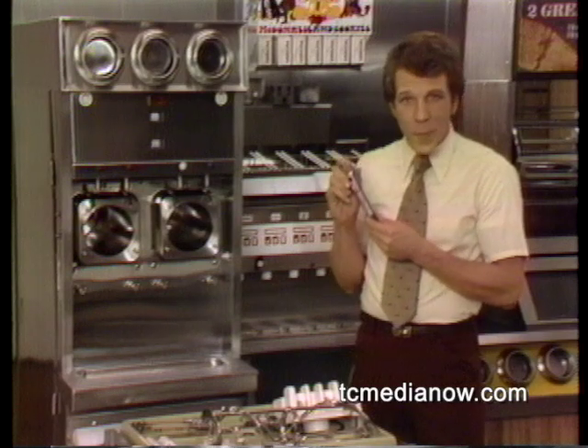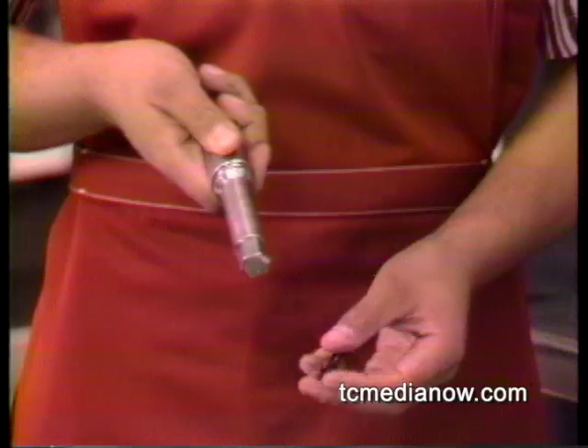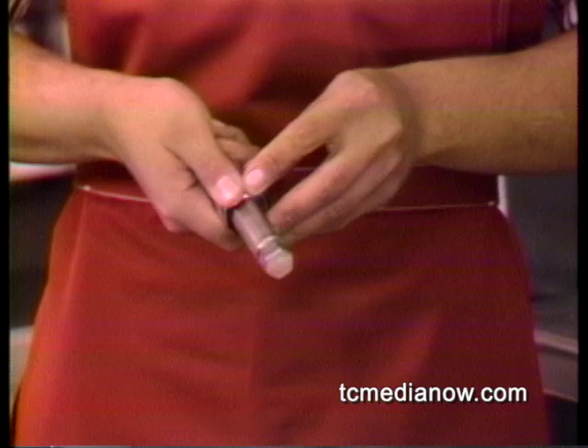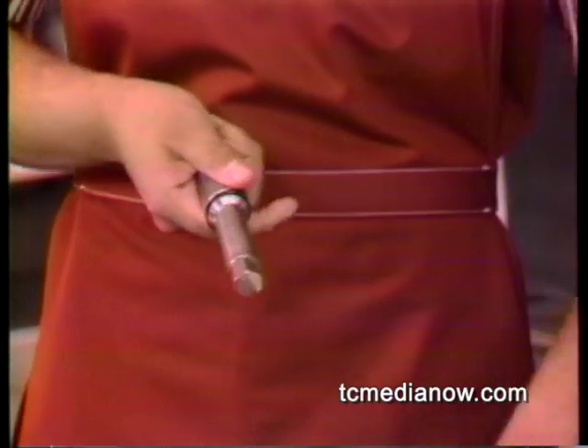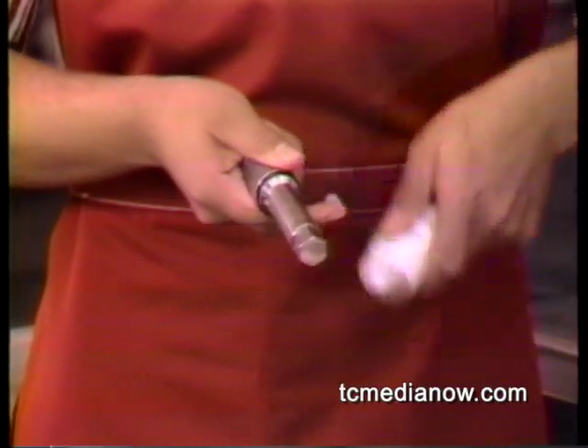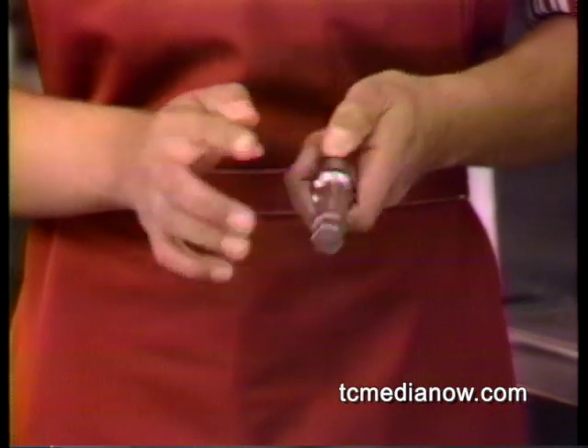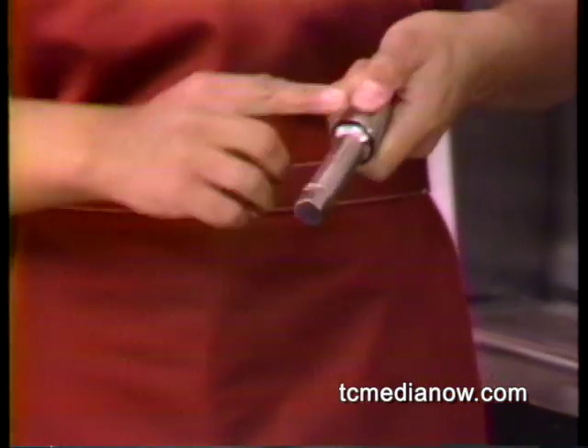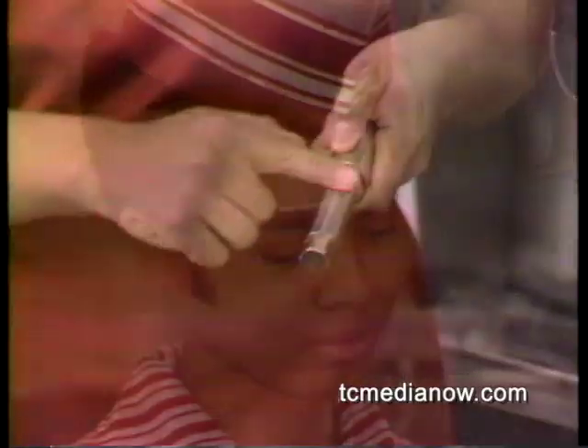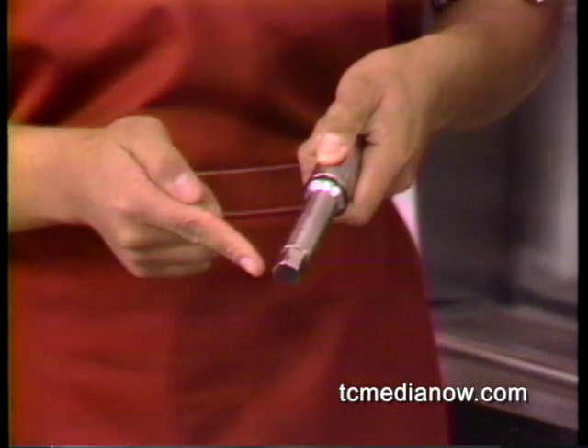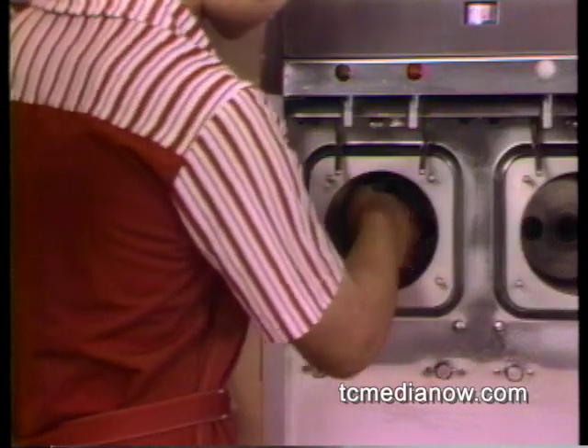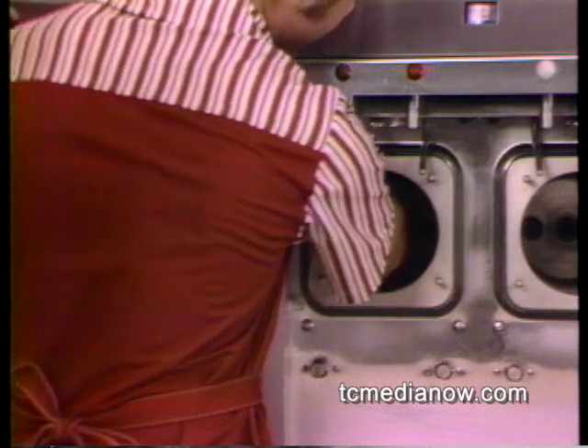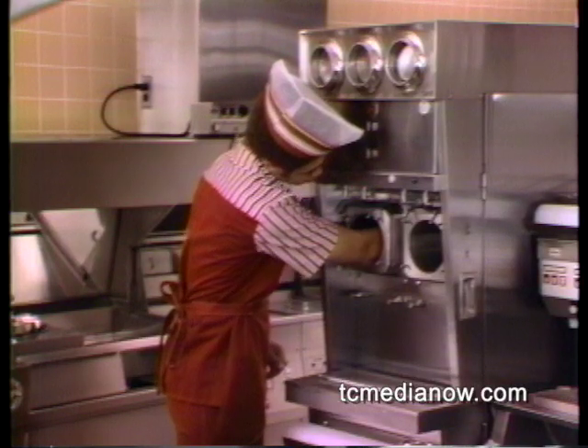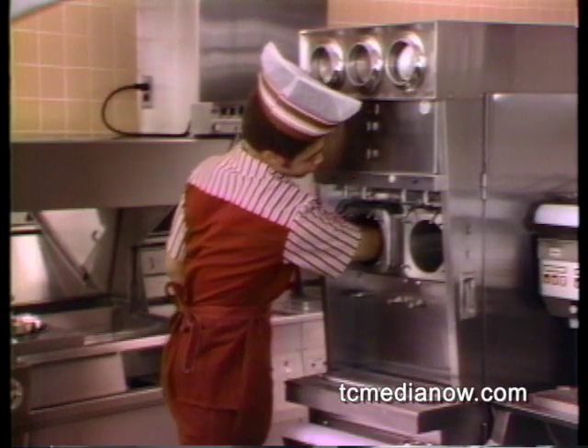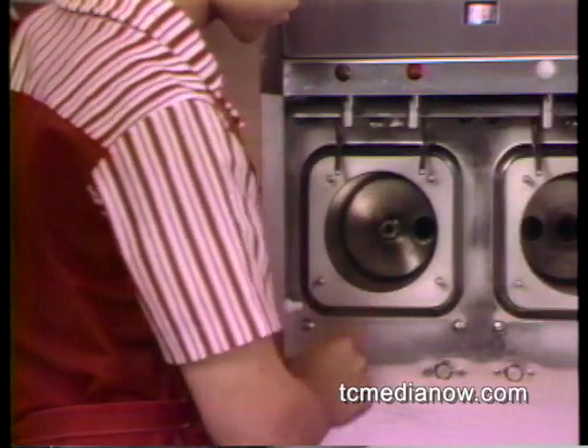Next, you'll want this part, the drive shaft. You'll need to slide the O-ring into position. Lubricate the shaft and the O-ring to within 1 inch of the hex end. But do not lubricate the hex end itself. Next, insert the drive shaft through the rear shell bearing at the back of the freezing chamber and engage the hex end firmly into the gearbox coupling.